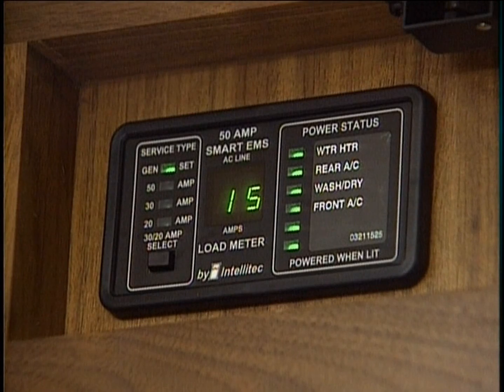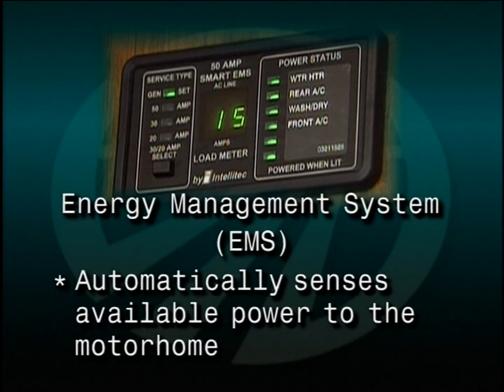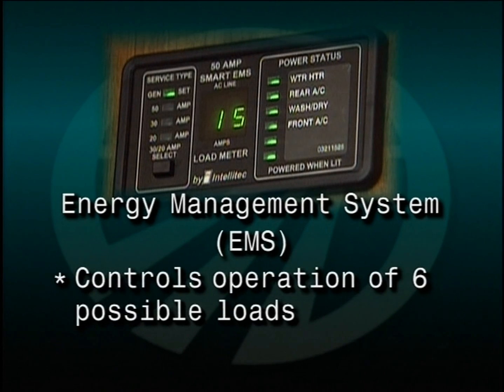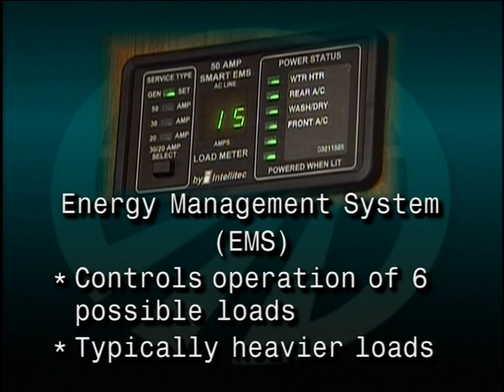The 50 amp EMS automatically senses the available power to the motorhome. It determines whether it's connected to a 120 volt 30 amp or 50 amp shore power source or generator power. Depending on available power, it controls the operation of 6 possible loads, as indicated on the distribution panel. These may be any type of load, but are typically heavier loads, those whose use can be postponed until a time when current is available for their use.